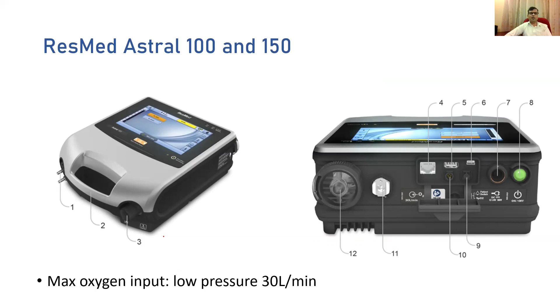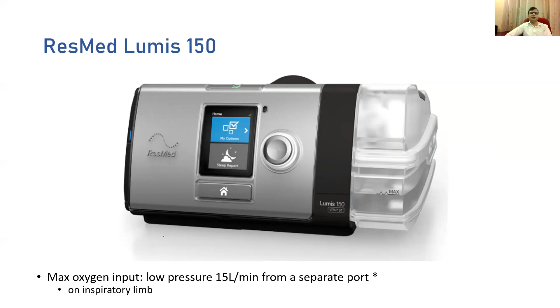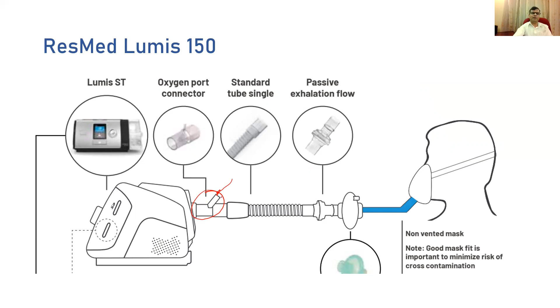And this is the other device, the ResMed Astral. It also can handle about 30 liters per minute of oxygen, so you have a low flow oxygen attachment. Now this is the Lumis 150. There is no dedicated port in the device, so you attach a certain piece like I showed you before, and then add about 15 liters through a separate port. This is far inferior to the Astral device in giving oxygen because there is no dedicated oxygen port on the device. So this is how it is attached. You attach this piece and connect oxygen into that port.